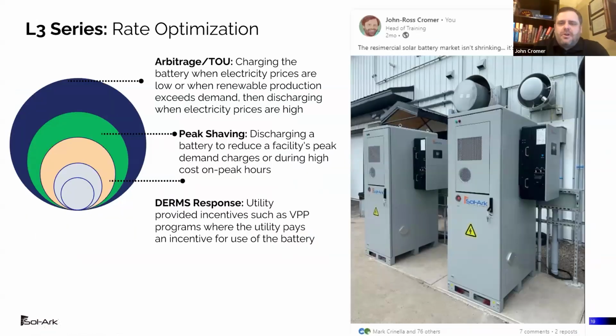Okay, so popular applications of Sol-Ark. While we can do these very large systems, and we do very large systems, even before our commercial product line, we were doing three-phase commercial service with our residential. So our commercial line dramatically simplifies the three-phase projects. But very popular three-phase applications are time of use metering in California, or peak shaving, which is my favorite application, because if you have high demand charges, that can provide the very best payback in the industry, as well as DERMS response and utility programs.